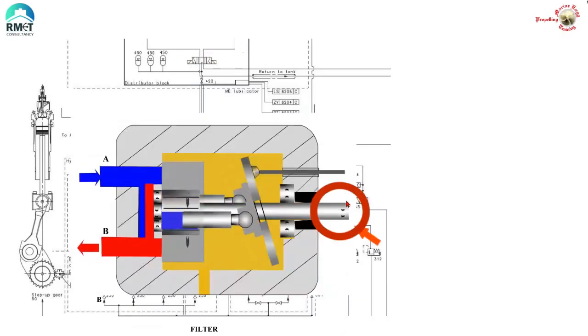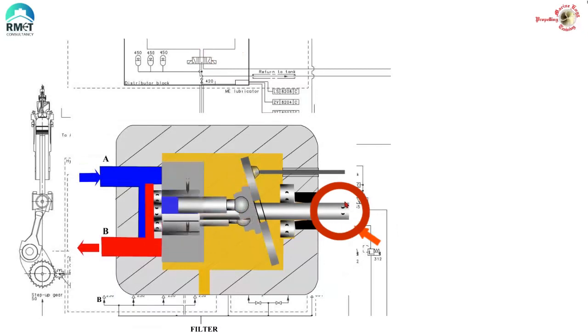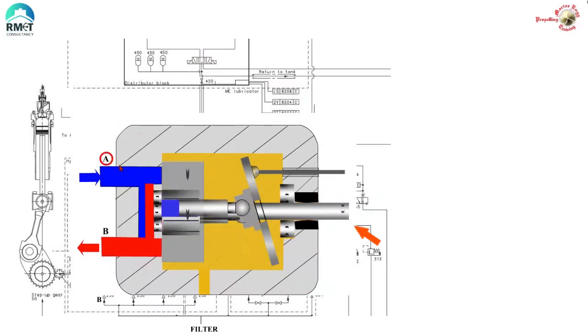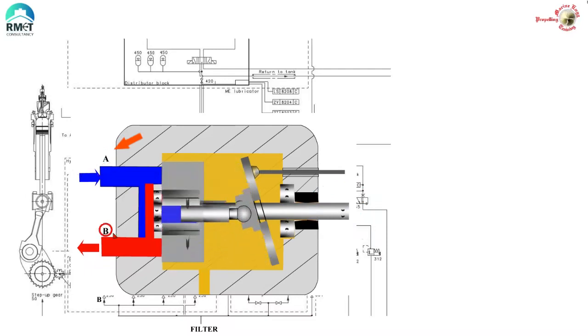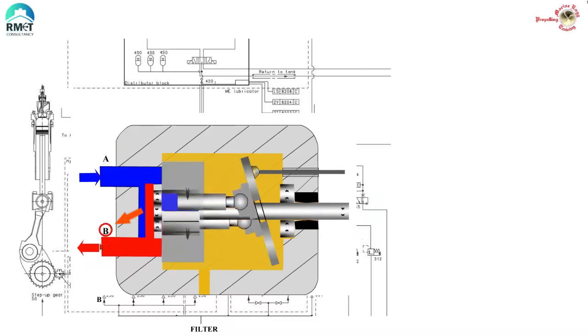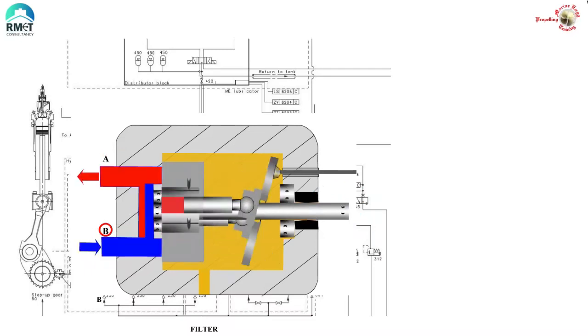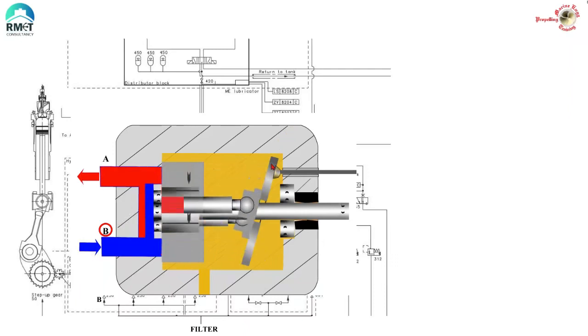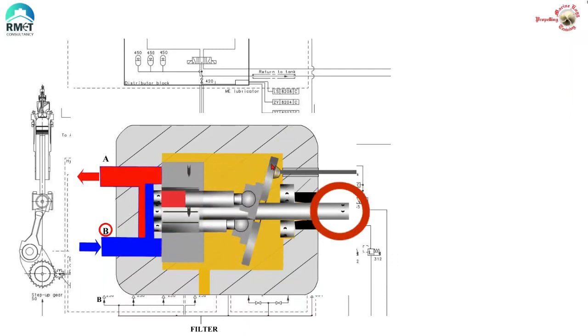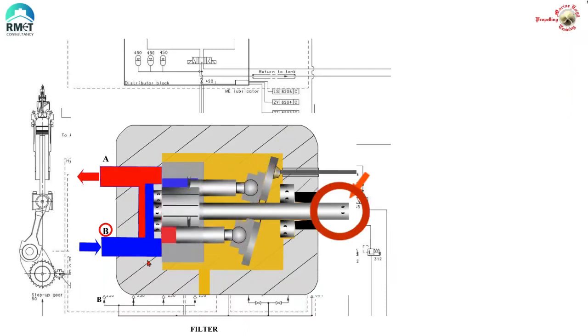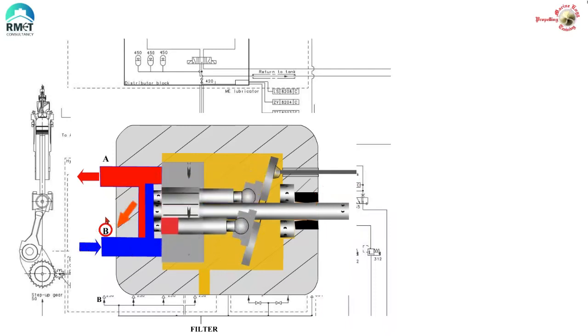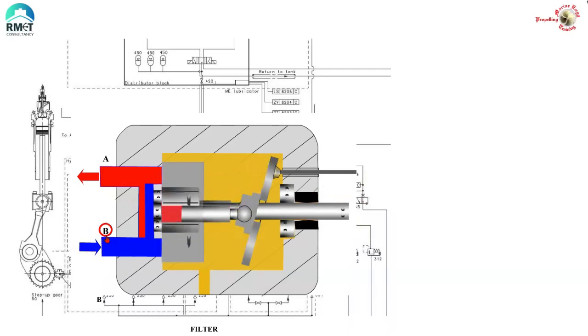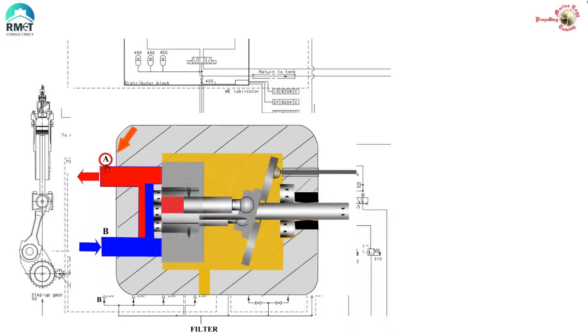Here, you can see that the pump is rotating with the shaft in anti-clockwise direction and the suction is from the A side and discharge is going to the B side. Now, if we swing the swash plate to the right, note that the shaft rotation is constant. It is still the same anti-clockwise. Now the pump takes suction from B side and discharges into the pipe A.